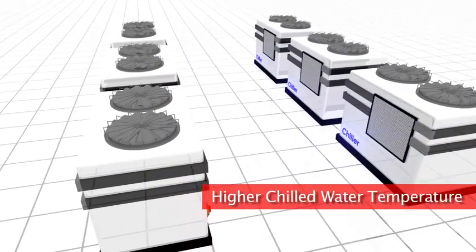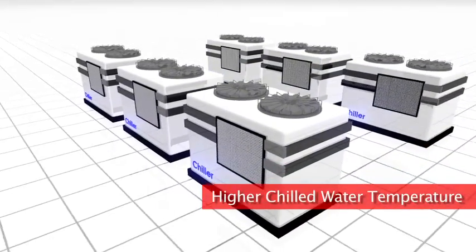This for us meant that we could get between four to six thousand hours a year of free cooling and that directly translates into about a million dollars a year in terms of power saving once the facility is full.